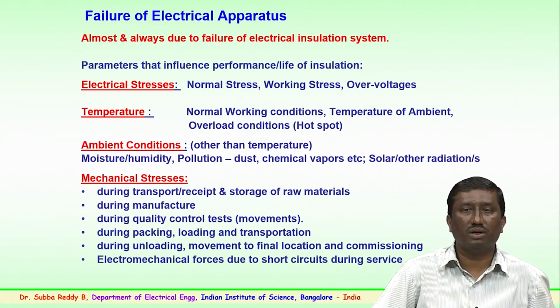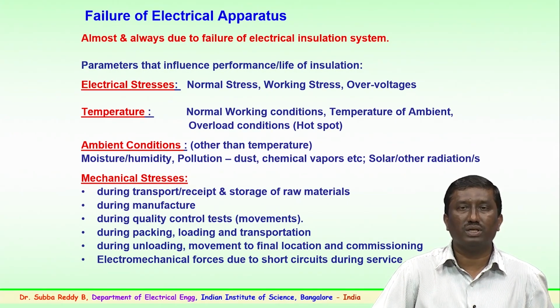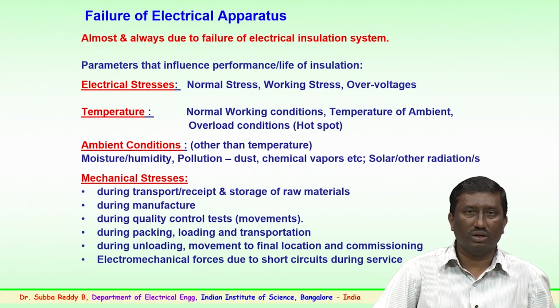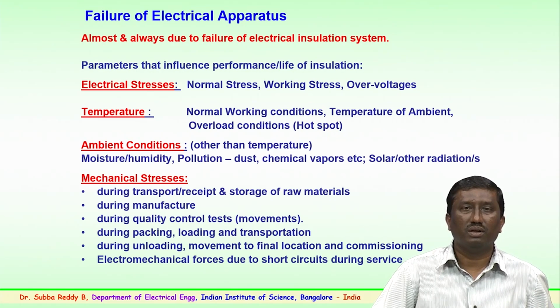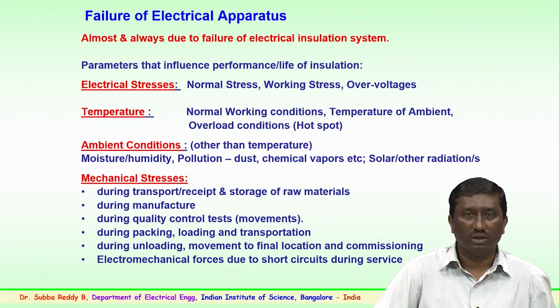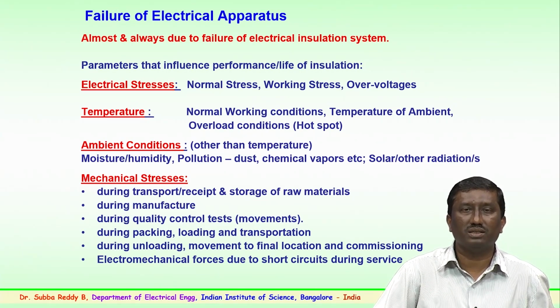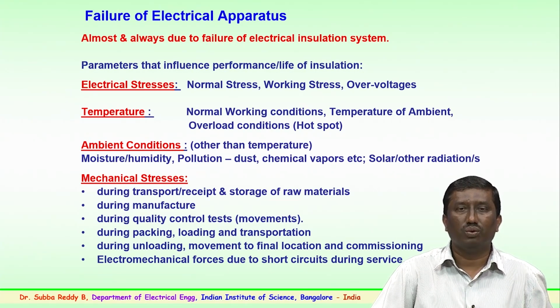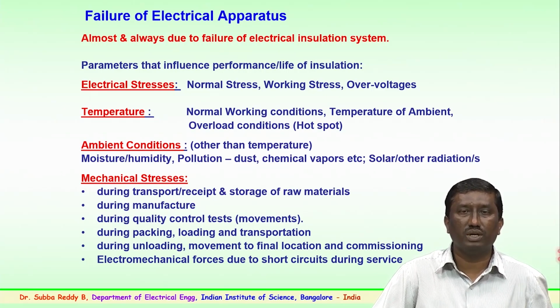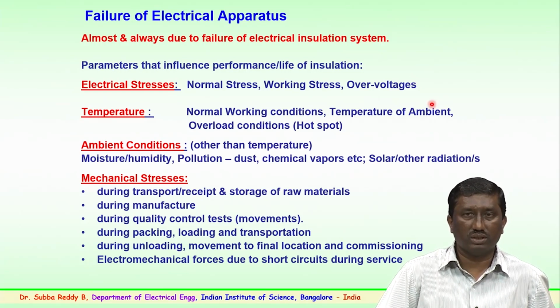So, what are the failures of electrical apparatus or any high voltage apparatus which are normally observed in the field? It is known that almost always the failures occur because of the electrical insulation system. Some of the parameters which could influence the performance or the life of the insulation are the following. Number one is the electrical stresses. The insulation of the equipment could lose its performance over a period of time. This is due to the normal working stress continuously over a period of time or due to over voltages. So, the insulation which is in continuous stress and also takes over voltages may lose its properties over a period of time because of continuous electrical stress.